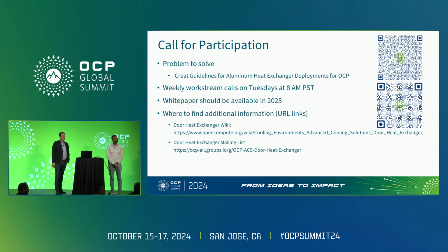Yes, thank you. With regard to the corrosion protection, I think you mentioned you're beginning a test soon. I was wondering what testing you have done so far with existing PG25 fluids and what you have seen. Yeah, we have experience based on our automotive experience for sure. We succeeded with a Japanese car maker on different requirements. Today we have to extend this experience to data center conditions.